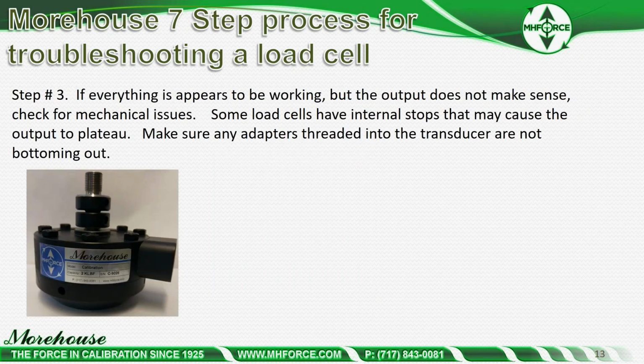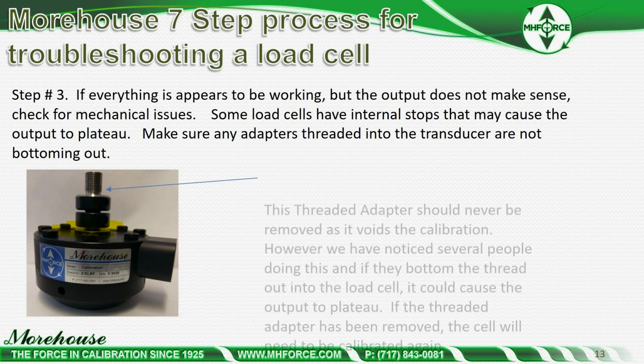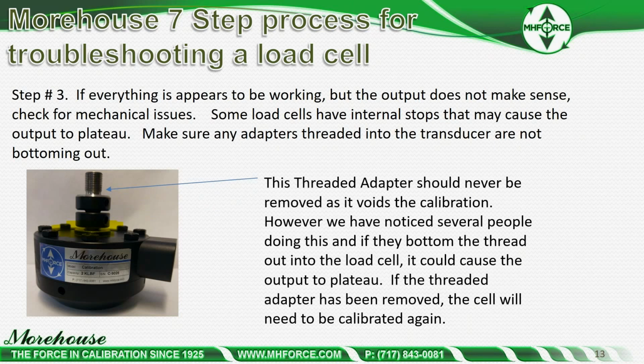So if everything appears to be working, but the output does not make sense, check for mechanical issues. Some load cells have an internal stop that may cause the output to plateau. Make sure any adapters threaded into the transducer are not bottoming out. If you look at this picture, right here's what we're talking about. This is the threaded adapter, and it should never be removed as it voids the calibration.